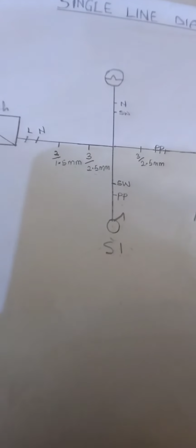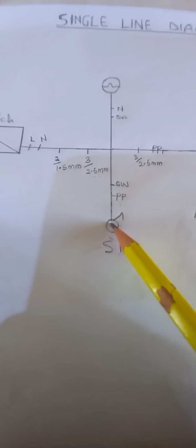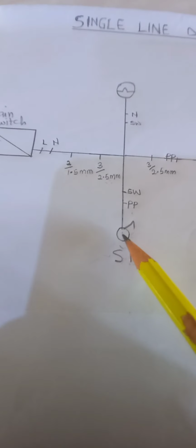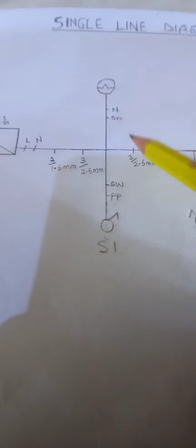And then PP means parallel lines, or strappers. Whenever you see PP, it means parallel. Because we need to connect these switches together to be able to control this lamp, there are wires called parallel lines. This switch contains 3 terminals, this contains 4 terminals, and this also contains 3 terminals. So of these 3 terminals, one will connect to the lamp as the switch wire, and the other 2 will connect to the intermediate, that is the parallel lines or strappers.